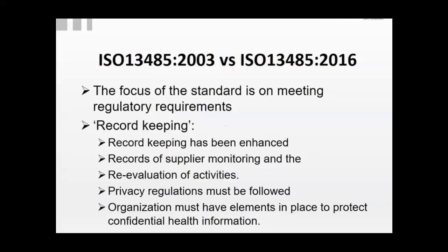Okay, so that was what I mentioned earlier. If you have an outsourced supplier for your product, for example sterilization, or raw materials coming into your facility, you have to keep records of how you monitored them. Did you go audit them? Did you get the documentation of their processes and procedures, and all that? All those records need to be kept. Evaluation of activities: if you do something and it failed, you try to fix it and do it another way. Did you go back and reevaluate to see that it worked?